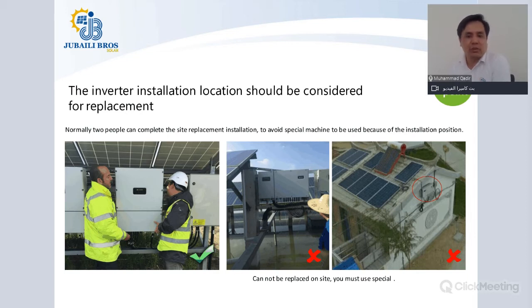On the right side, in the picture shown, the inverter is installed at a very big height, and accessing the inverter becomes very difficult in that case. Even going up at that height is difficult. Similarly, in the floating PV plant, again the inverter is installed at a location where accessing it is difficult, and removing it would be similarly difficult. So the best case is the picture shown on the left side in this slide, where you can easily access the inverter, dismantle it, and take it out.